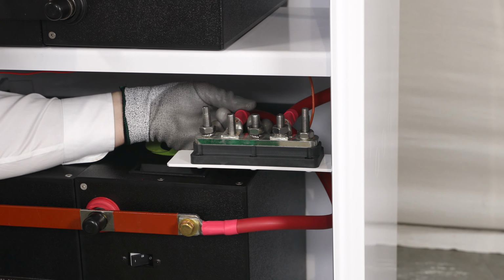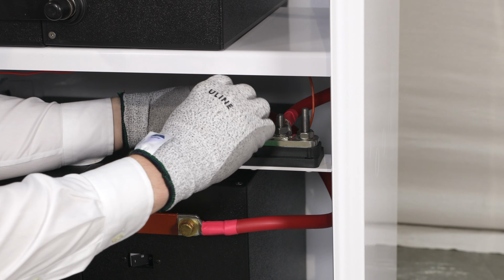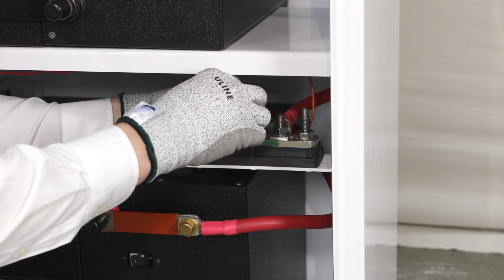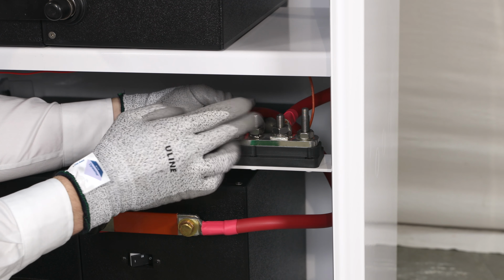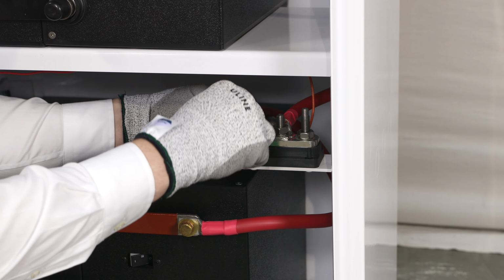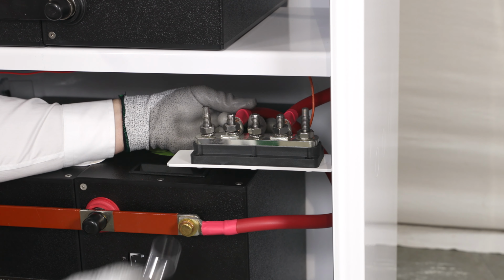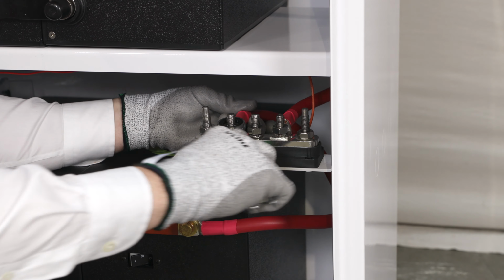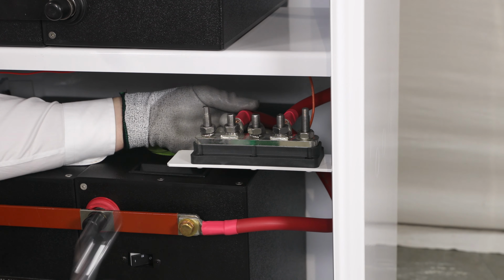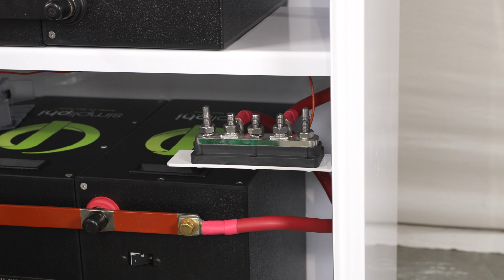This cable will not be routed through the gap between the shelf and sidewall. Attach the cable's lug to the 5-point terminal block, followed by the lock washer and nut that were removed earlier. Firmly tighten the nut to secure the cabling lug to the 5-point terminal block. Now, both positive bus bars should be secured to the 5-point terminal block.